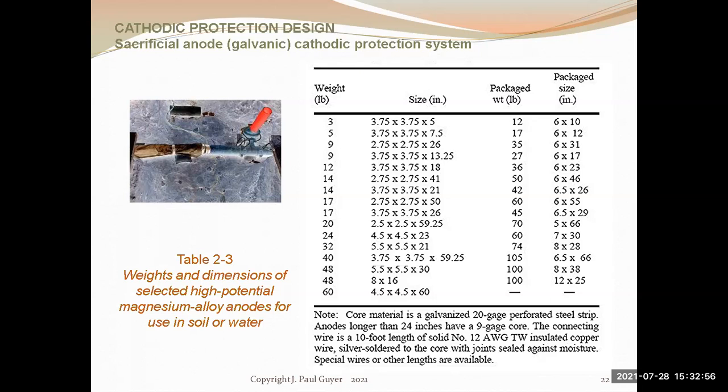And this, with time, can result in the anode rod corroding all the way through, and that breaks the electrical connection between one end of the rod and the other. And you end up having a rod there in the ground that's only half the size that you thought it was, and you wonder why your system isn't working that well. So it's the carbonaceous backfill. It increases the capture efficiency, and it increases the uniformity of contact of the rod with the negatively charged oxygen ions.